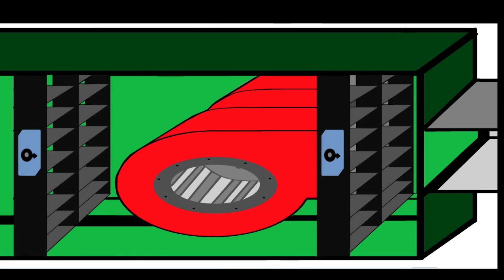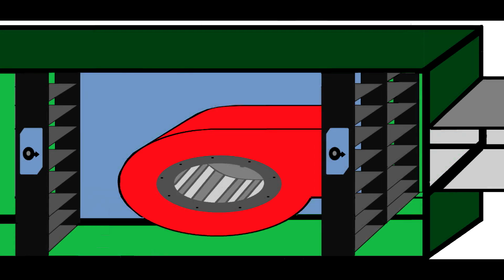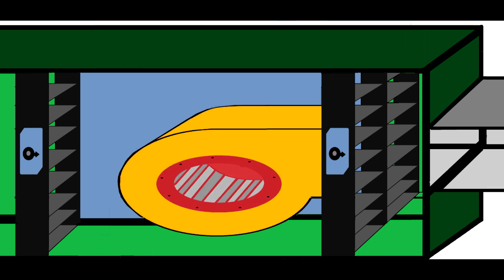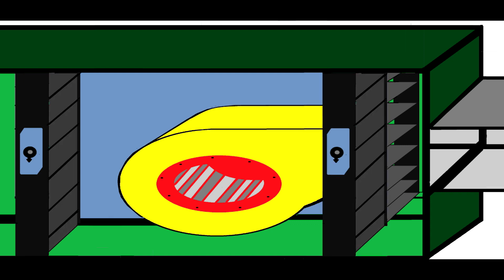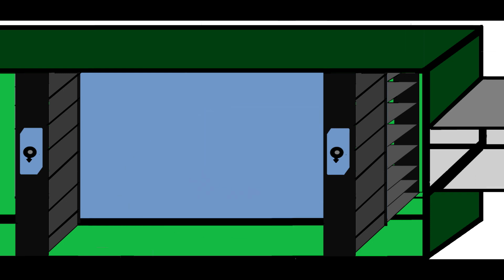I just want to tell you that these fans are hot. They will heat the supply air chamber, but they will run on negative pressure, which is better than the other one. I decided to segregate the spaces again. The reason I'm doing this is because if this fan fails, I will have the capability to isolate the fan and then replace it without stopping the production, without disturbing the airflow. As you see here now, the damper just closed, and I could remove the fan, and the other fan on the other side will push the required quantity of air.